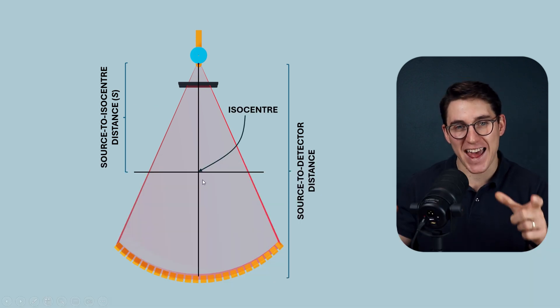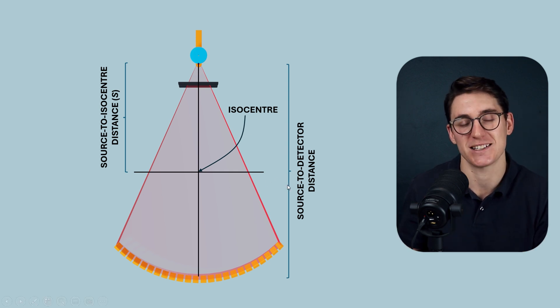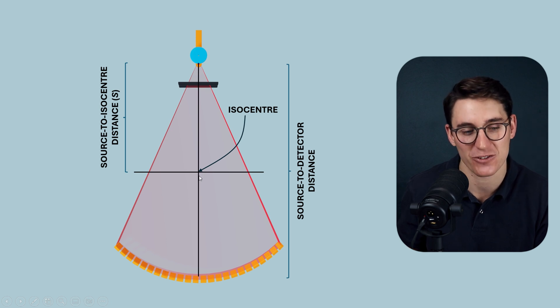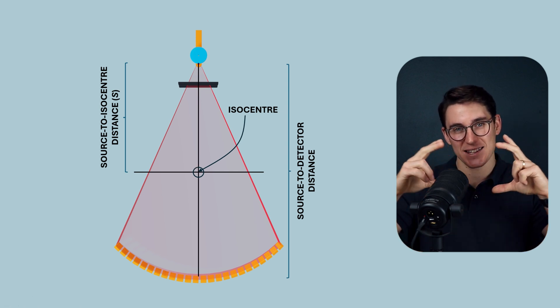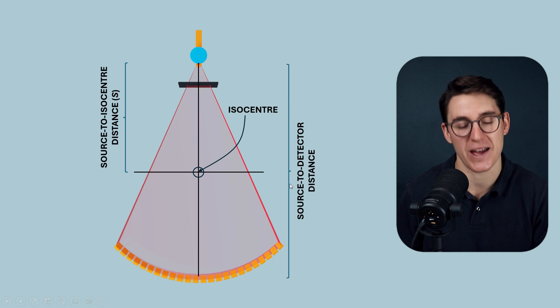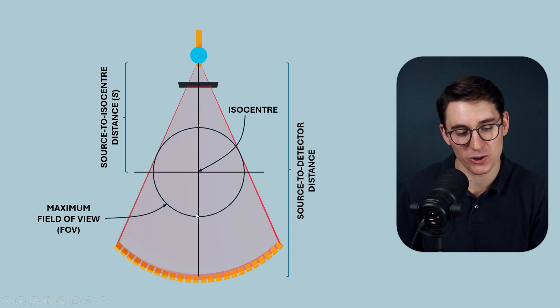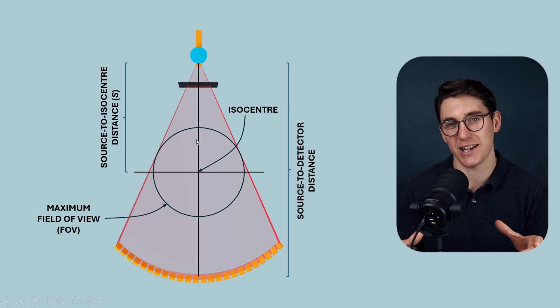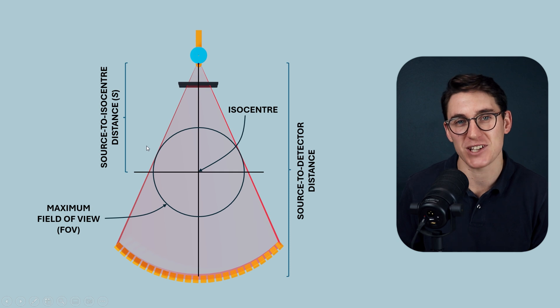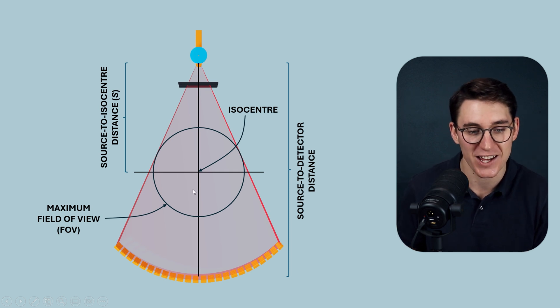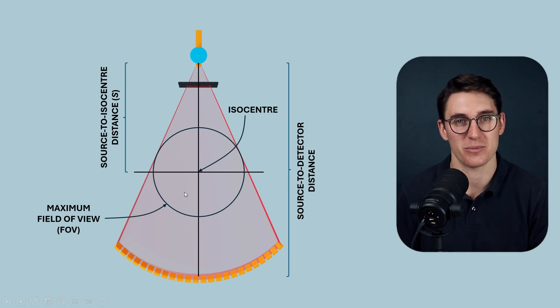Importantly, the isocenter is the axis of rotation for a third generation CT scanner. It's often halfway from the source to detector distance, but it doesn't have to be. If we draw a small circle around the isocenter and expand that circle out until it hits the edge of our fan beam, we create what's known as the maximum field of view — the area in which we can accurately calculate attenuation data. Anything outside this maximum field of view cannot be accurately processed, so our patient needs to sit within it.